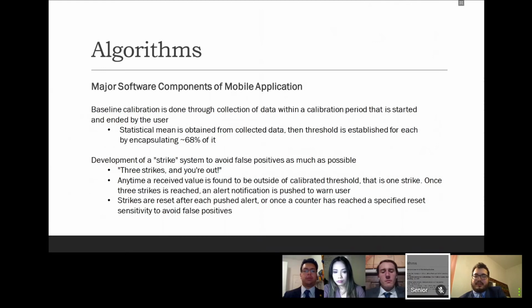The second algorithm developed was a strike system to avoid false positives as much as possible. Anytime a received value is found outside the calibrated threshold, that counts as one strike for that sensor. Once three strikes are reached, an alert notification is pushed to warn the user, indicating which sensor it came from. Strikes are reset after each pushed alert, or once a counter reaches a specified reset sensitivity, in order to avoid false positives.